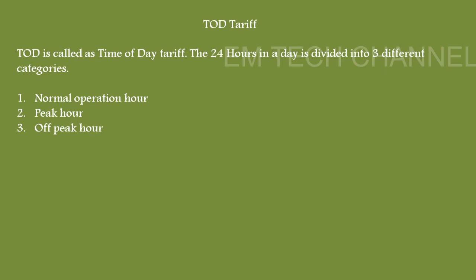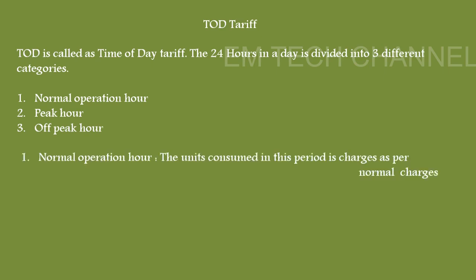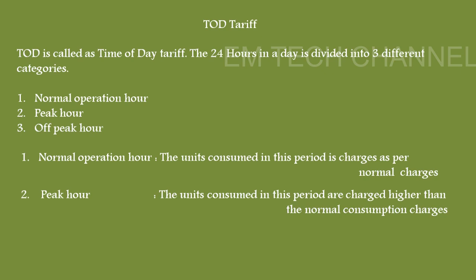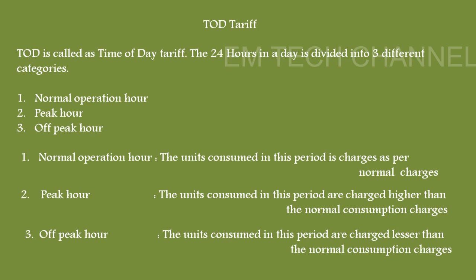This type is called TOD tariff. This is a special type of tariff levied on consumers based upon the time zones in which they are consuming energy. TOD stands for Time of Day tariff. In this, the 24 hours in a day are divided into three different categories: normal operation hour, peak hour, and off-peak hour. Normal operation is where units consumed are charged at normal tariff rates, peak hour units are charged higher, and off-peak hour units are charged lesser than normal consumption charges.